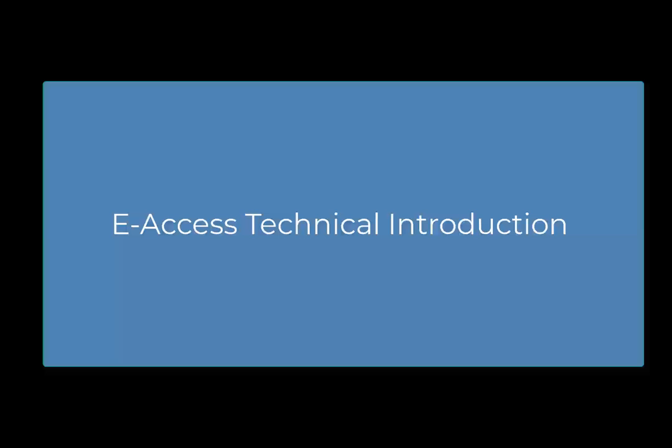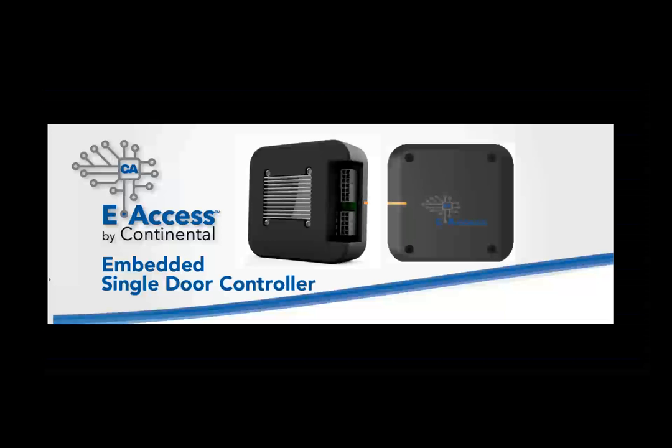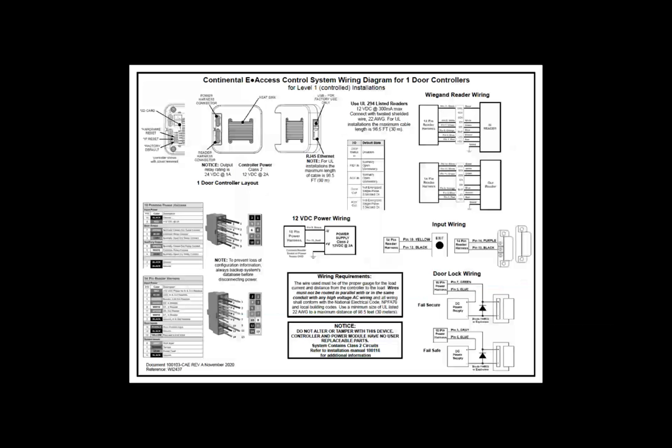The eAccess Embedded Single Door Controller supports 1 door with 2 readers. One reader for in and one reader for out. In addition, it contains 2 relays. One for the door lock and one for the auxiliary relay. It also contains 3 inputs. One for rex, one for door position switch and one auxiliary input. For complete wiring details, refer to the 1-door controller wiring diagram. The wiring diagram will display in detail each wire and their descriptions.